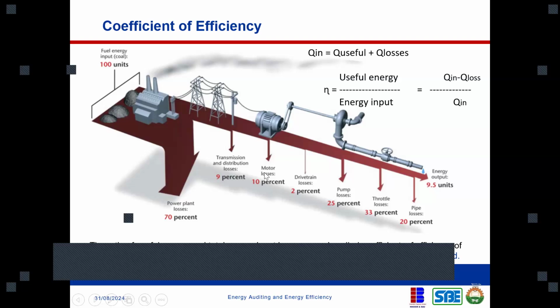The motor then drives a pump, motor and pump are not the same thing. When the motor drives the pump, there could also be losses in the pump, which in some cases could be as much as 25%.